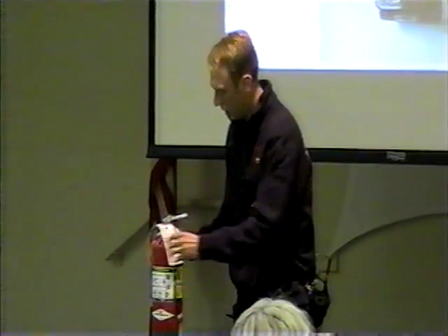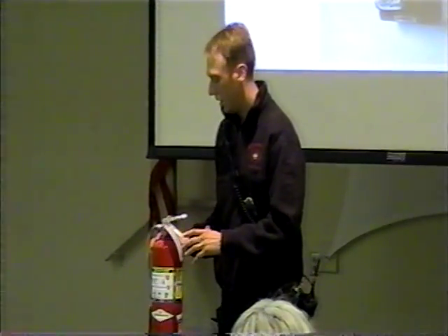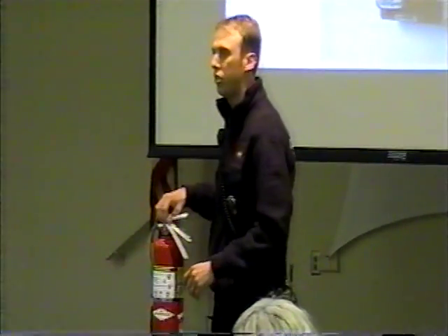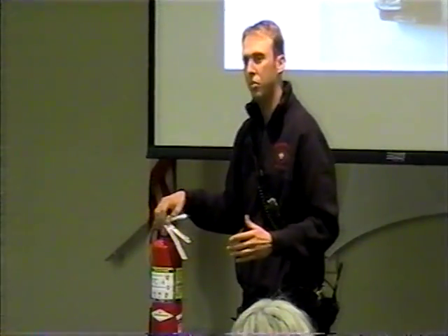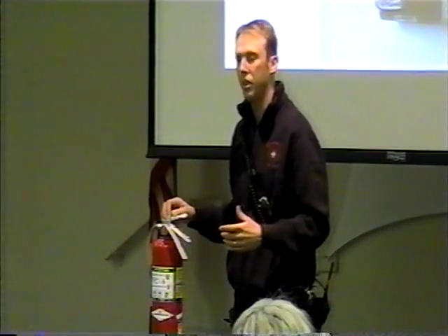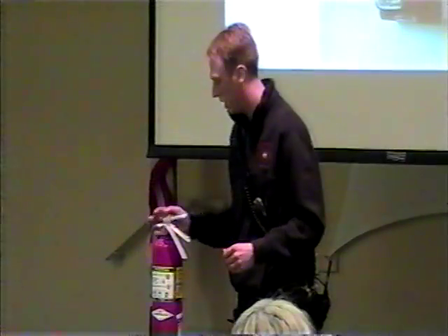Now before you use a fire extinguisher, there's a few things you got to check first and think about first. First thing to check is, like I said, the type of extinguisher. Make sure it's the right extinguisher you need to use. Second of all, you need to look at the gauge here and make sure it's charged. Sometimes these, when they sit for a while, or if they weren't properly sealed or manufactured, they can leak a little bit. So you want to go in there with some pressure in your extinguisher.